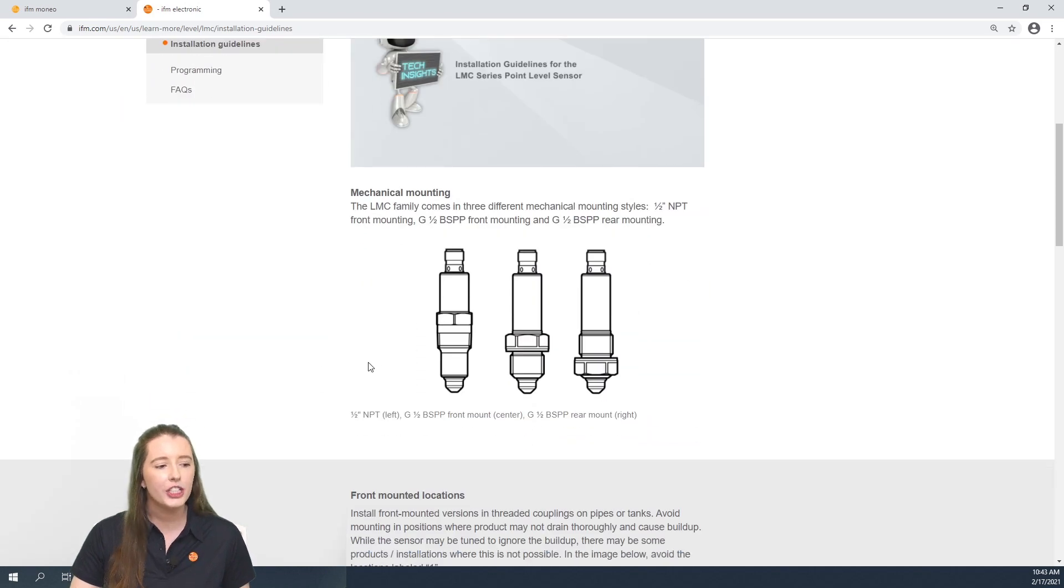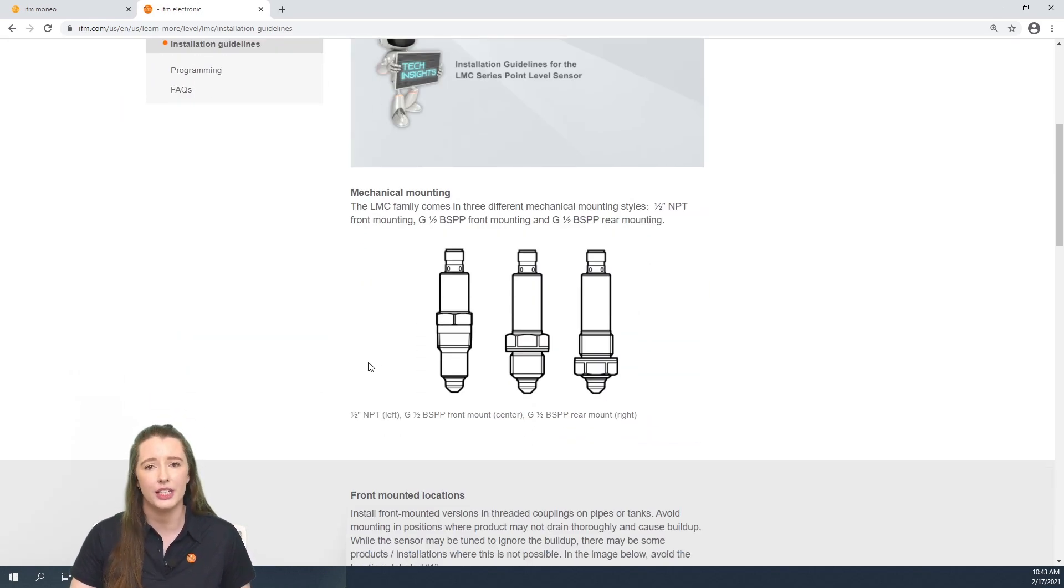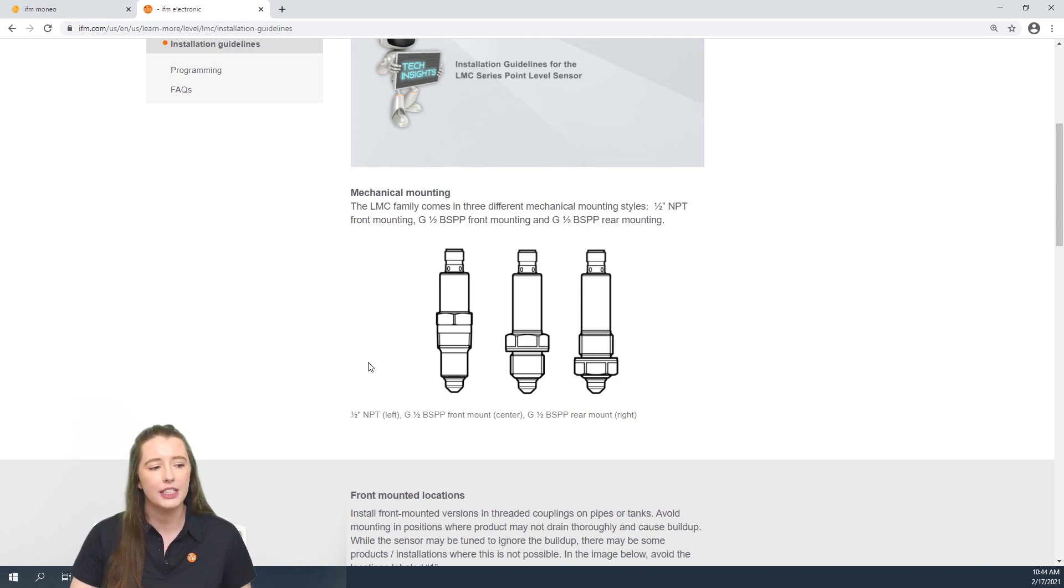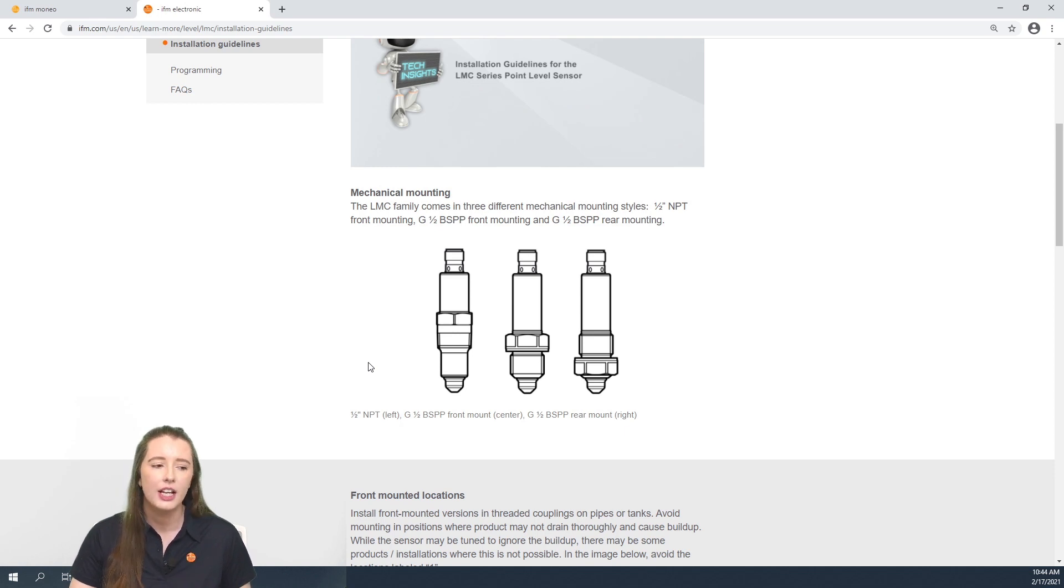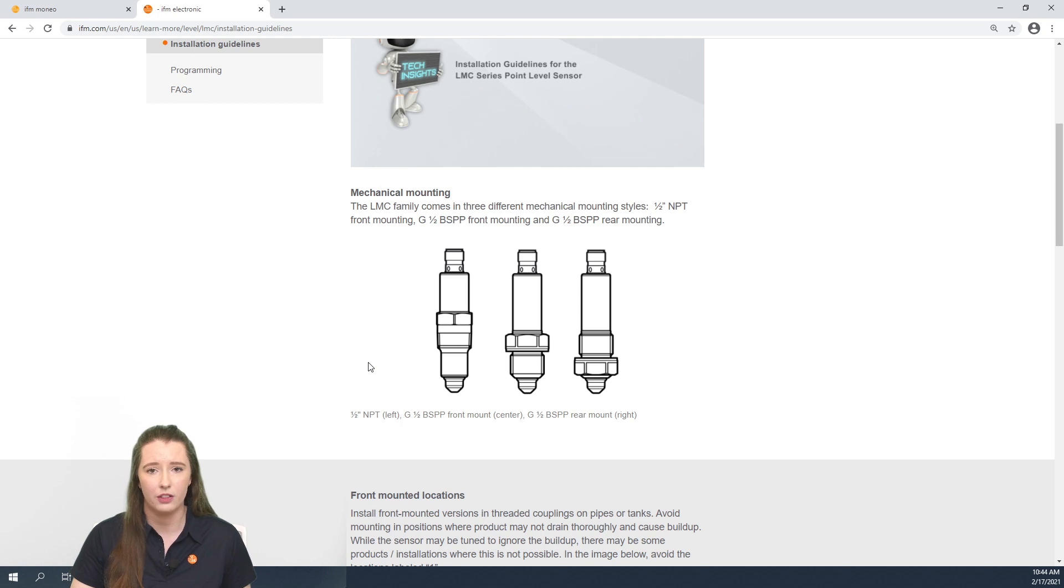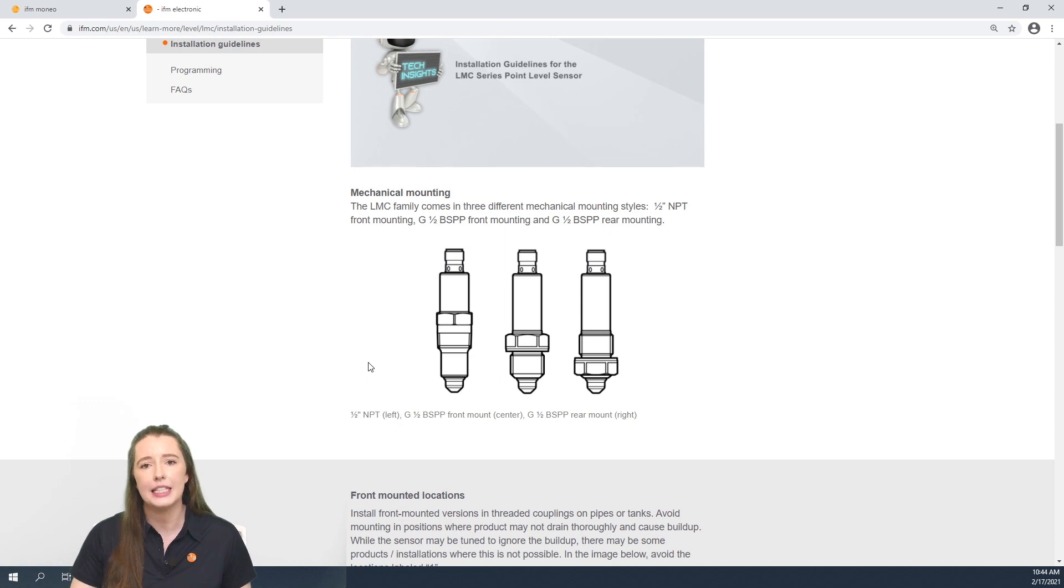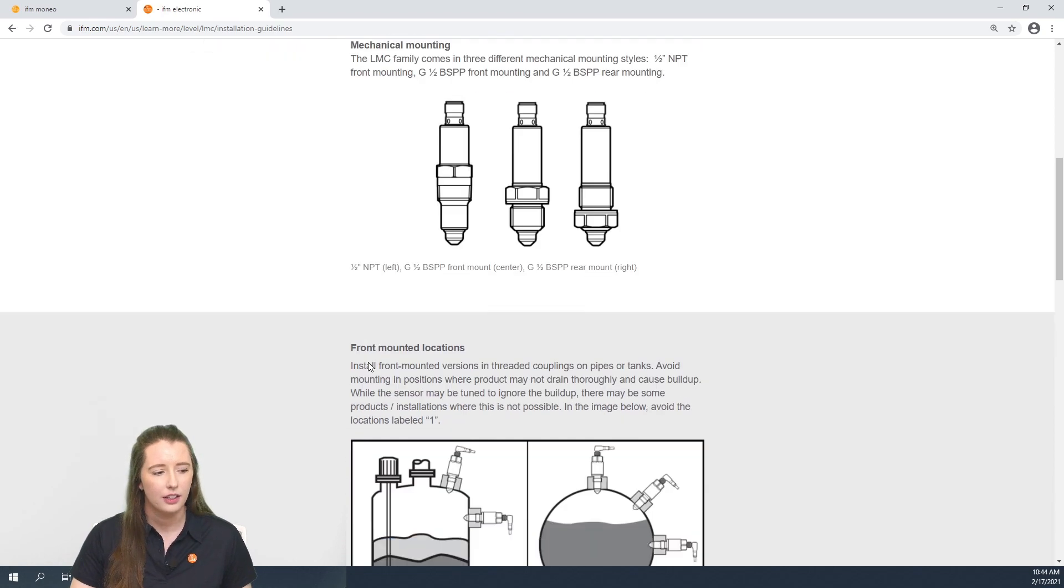The first thing to note is that we have three different process connections available. The first is the half inch NPT front mounting version. The second is the G ½ BSPP front mounted version, and the third is the G ½ BSPP rear mounted version. BSPP stands for British Standard Parallel Pipe Thread versus the NPT tapered thread.